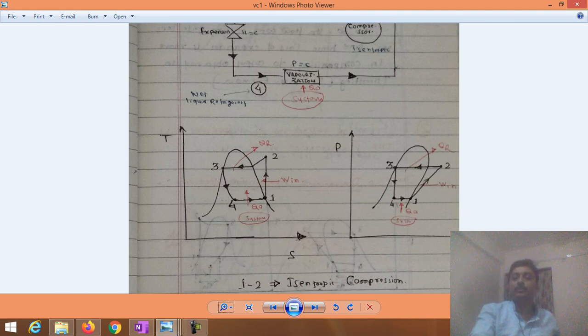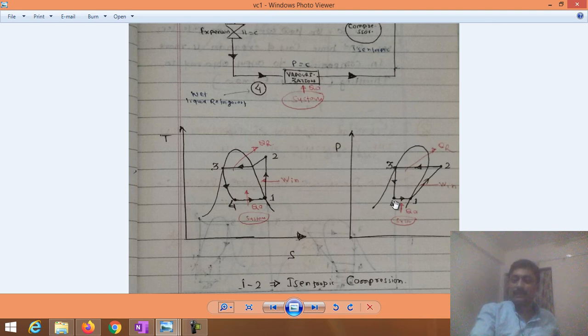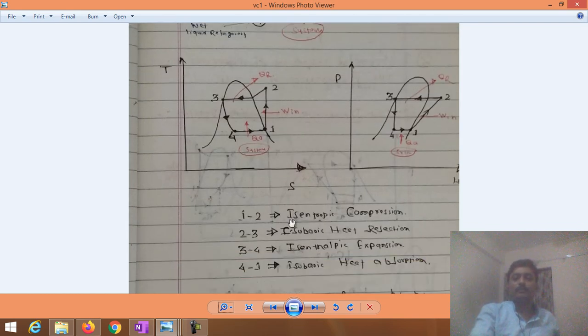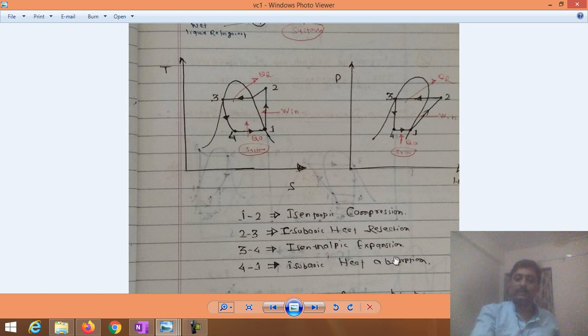This process can also be seen on a P-H plot. On the x-axis, enthalpy is shown, and on the y-axis, pressure is shown. Process 1 to 2 is isentropic compression; process 2 to 3 is constant pressure heat rejection in the condenser; process 3 to 4 is isenthalpic expansion in the throttler; and process 4 to 1 is constant pressure heat addition in the evaporator.